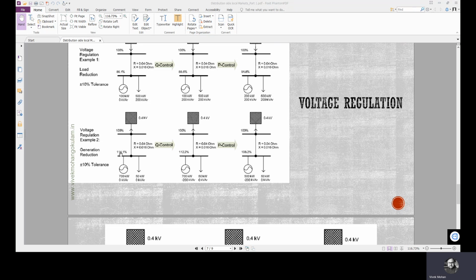Now, at present, the voltage profile at the local node is 114.1%. Now it is violating the tolerance limit of 10%. Then it should be actually in between 100 to 110, right? In between 100 and 110, but now it is 114.1%. So we are trying to control the reactive power from the local node side, or reactive power injection at the local node is updated now by having a consumption of reactive power of 200 kVAR.